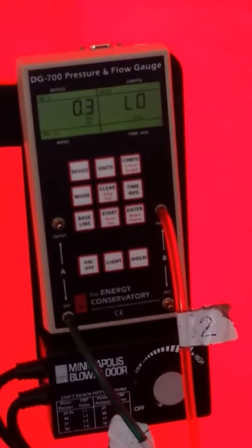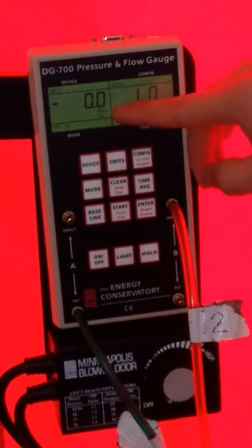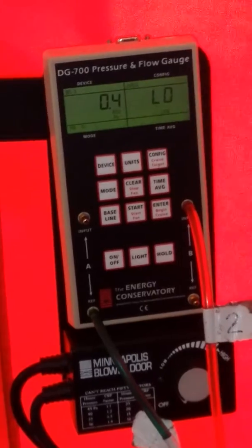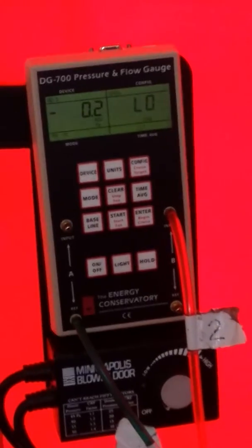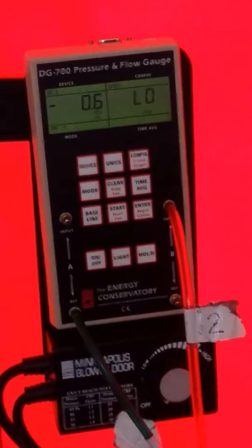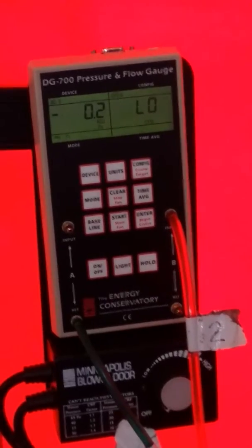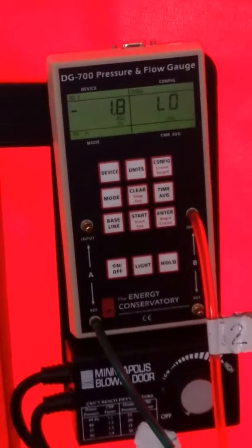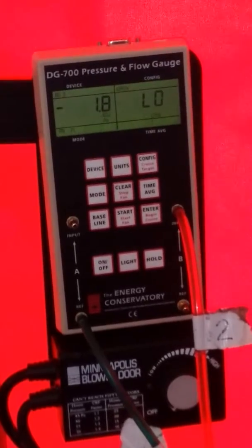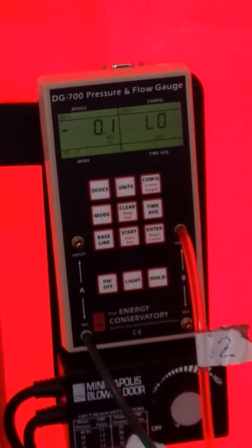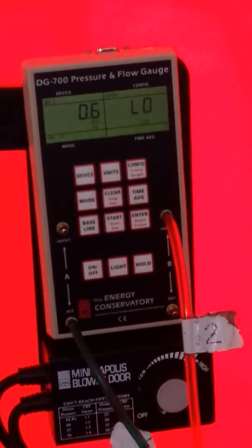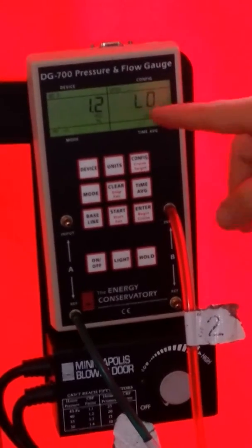Down below you'll see ADJ. The ADJ that we're seeing at the bottom is telling us that we have adjusted our baseline. So now, this is no longer showing us true pressure measurements. It's an adjusted pressure based on where we started with the stack effect and the wind going on. We found where the middle of that stack and wind were behaving on our house. We called that our adjusted pressure.